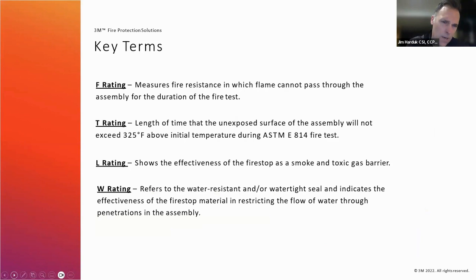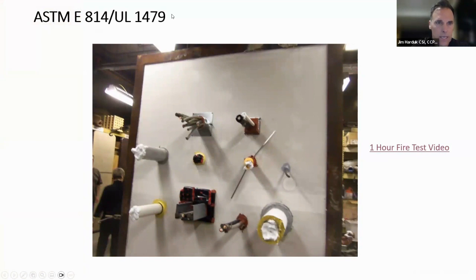But before we get into that, there are a couple more key terms I want to hit you with real quick. We're going to talk about F rating a lot. An F rating measures the fire resistance in which flame cannot pass through an assembly for the duration of the fire test. A T rating is the length of time the unexposed surface of the assembly will not exceed 325 degrees over ambient. An L rating shows the effectiveness of a fire stop as a smoke and toxic gas barrier. And a W rating is the water resistance or the watertight seal rating for that particular material. Next slide.